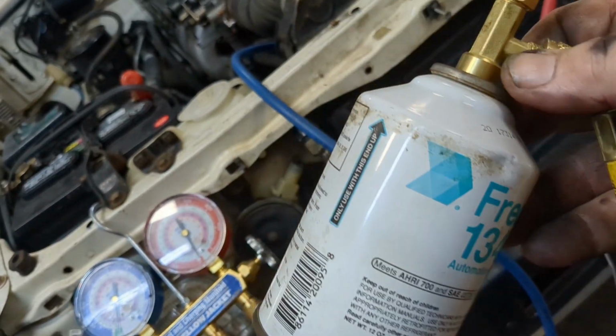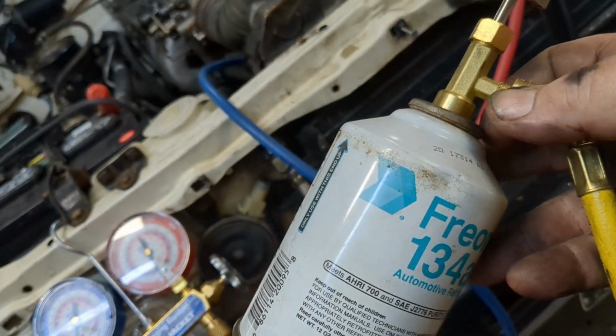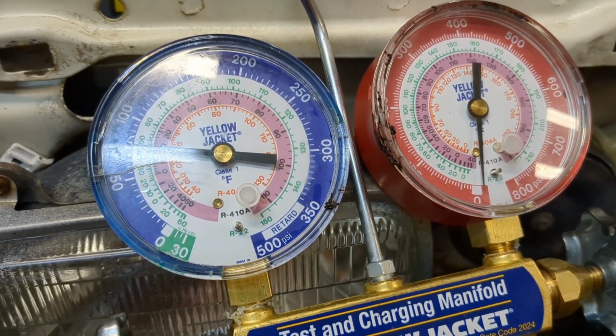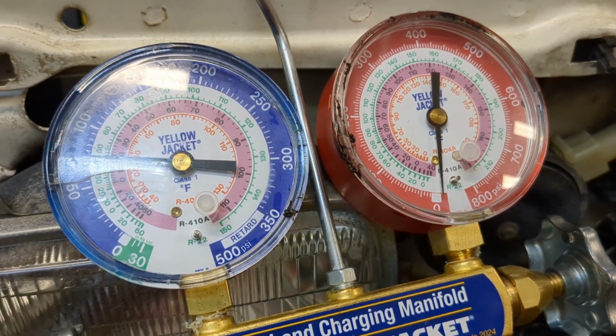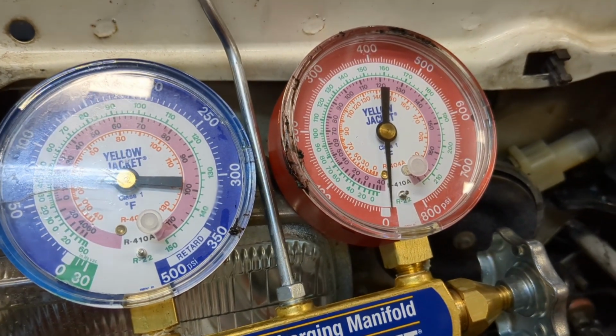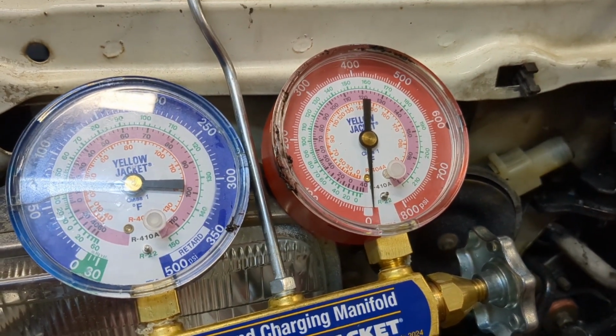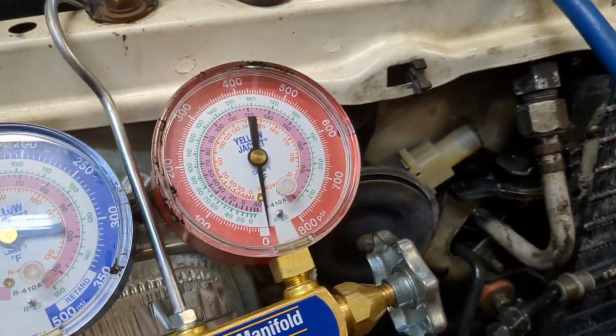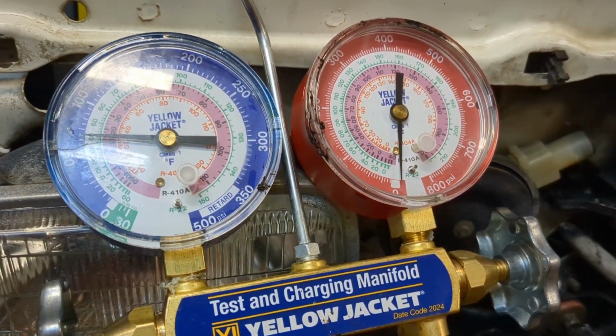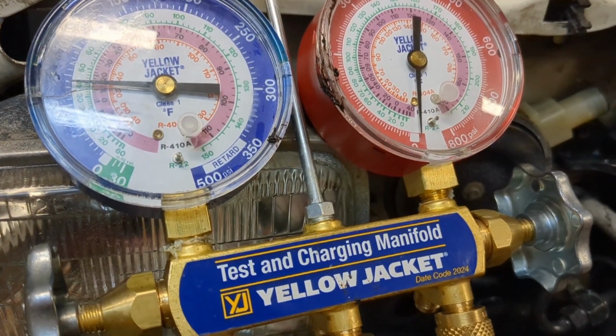And I got a good old-fashioned can of 134a that doesn't have that stupid self-sealing thing in it. Now what I like to do is static charge them first, because there's vacuum in the system. And by the way, that vacuum will eliminate all of that flushing solvent, all moisture. It's all gone with the vacuum.